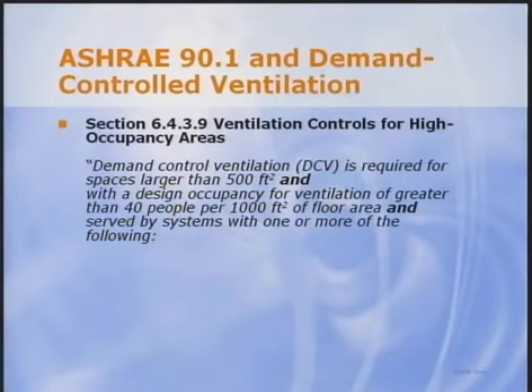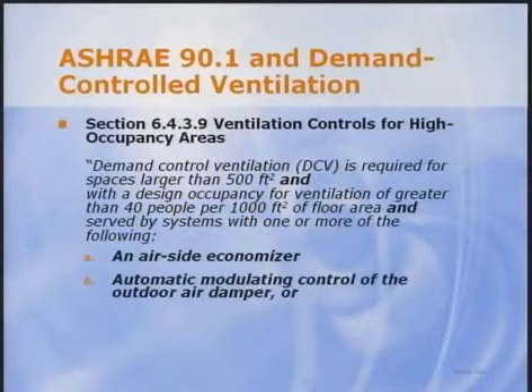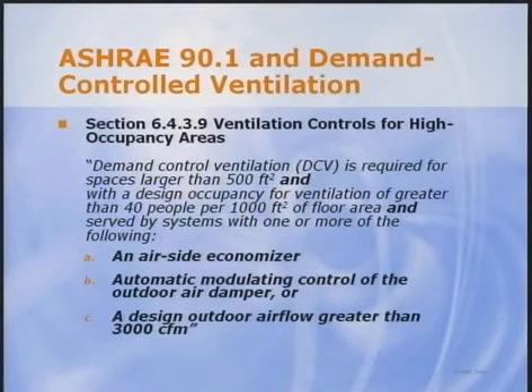When a space is larger than 500 square feet and has a design occupancy of greater than 40 people per 1,000 square feet, that's 25 square feet per person, then we have to examine the system. If the system has one or more of these, an air side economizer, or an automatic modulating outdoor air damper, or a design outdoor airflow greater than 3,000 CFM, then that space is required to have demand control ventilation. This was determined to be a viable system size for which the energy savings were significant enough to warrant requiring the additional sensors and control systems to reduce ventilation airflow when the space is partially occupied or not occupied at all.